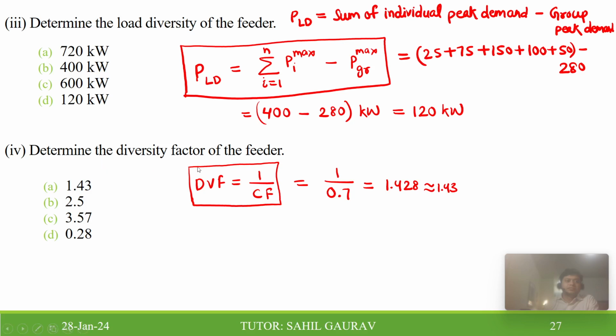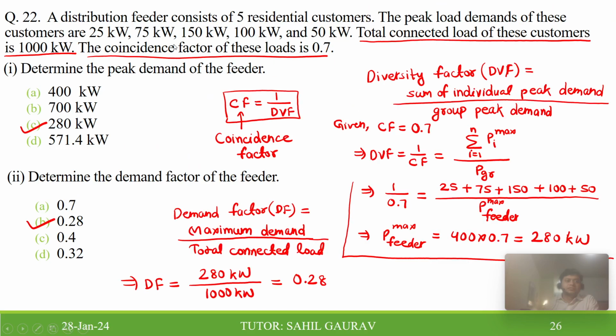So the group peak demand means the peak demand of the feeder, not of any individual customer. If you see here, this feeder consists of five customers, and they have given the individual peak demands. It is not necessary that whenever the peak demand happens, for example the third customer has a higher peak demand value, that it will be the peak demand for the feeder. That is an individual peak demand. So you have to find the peak demand of the feeder with the help of the data, and here the data is given as the coincidence factor.